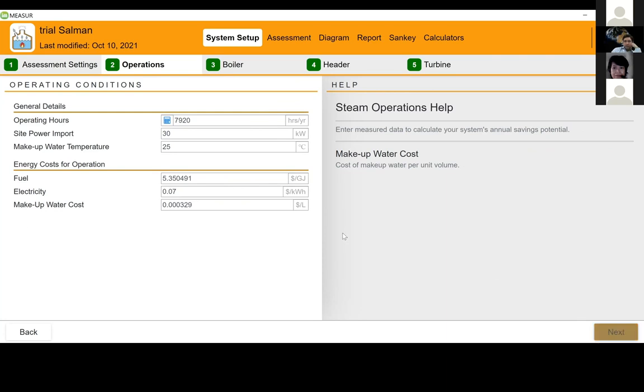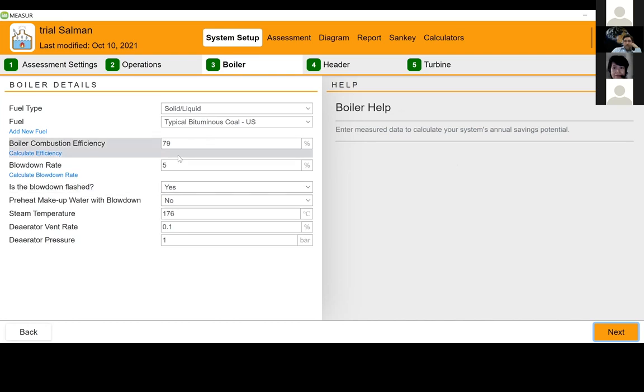currency. Then I went forward and I selected the type of fuel. So I selected solid fuel because I was using typical bituminous coal. The boiler combustion efficiency came from the stack analysis. And the blowdown rate was based on the data that was provided by the site engineer. And yes, the blowdown was being flashed. They were not directly doing anything, they were just flashing it. And they were not using blowdown to preheat the makeup water.